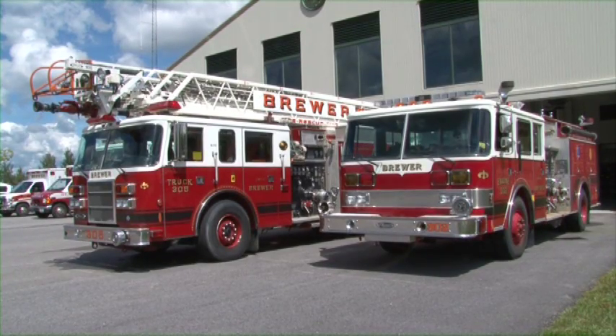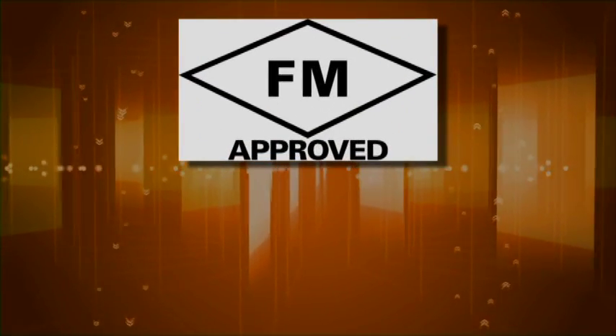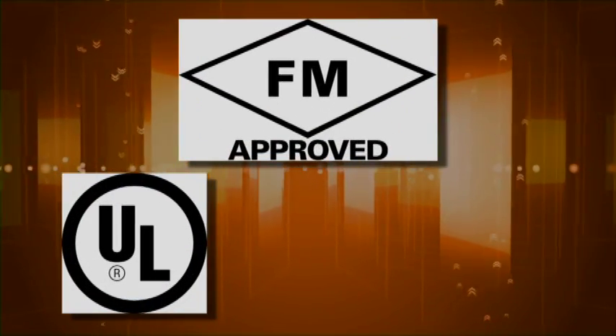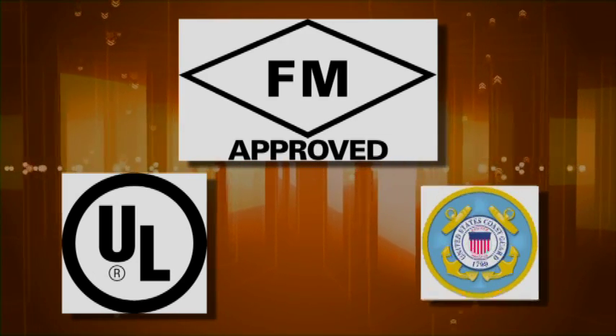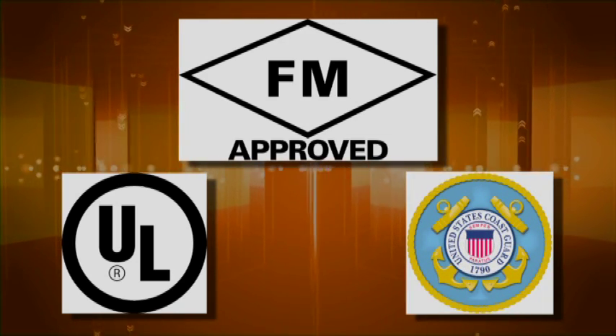Another thing to look for, an extinguisher should have an approval label affixed to it. Look for either the Factory Mutual logo or the Underwriter's Lab logo. Both are shown here on the screen. You may also find a Coast Guard label if a bracket is present.